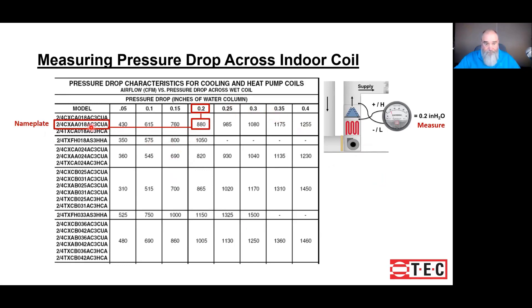In this example, the coil we tested had a pressure drop of 0.2, and our airflow estimate is 680 CFM. It is very straightforward — that's how you do it.